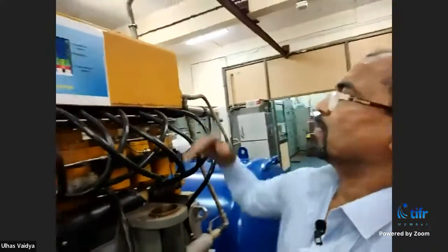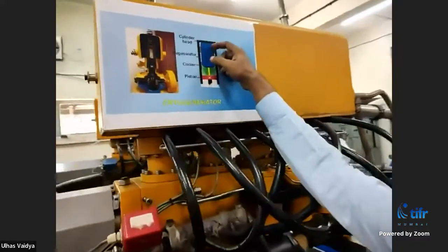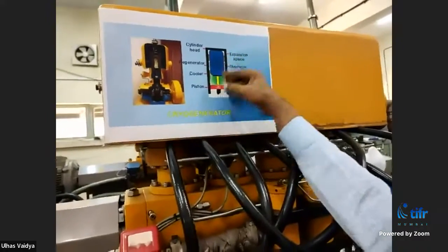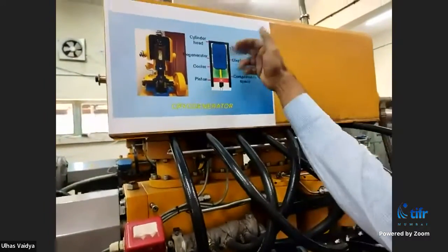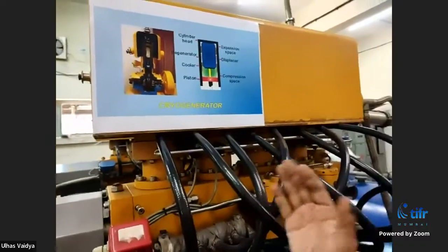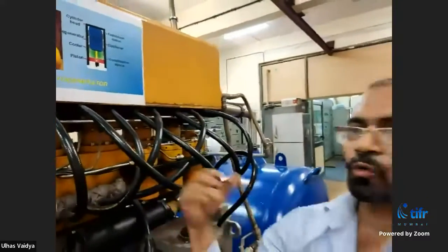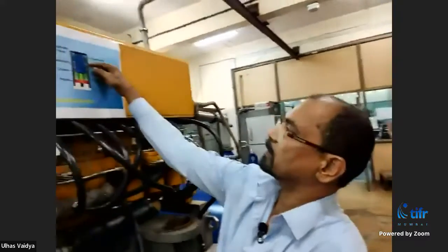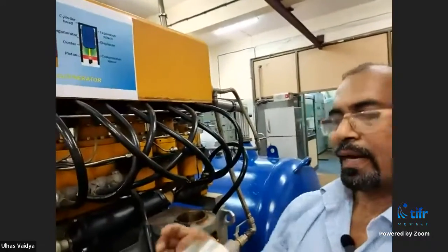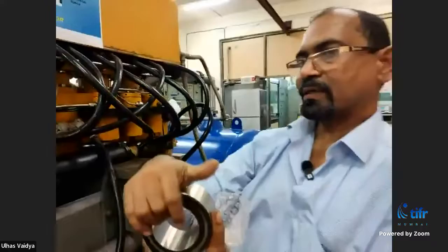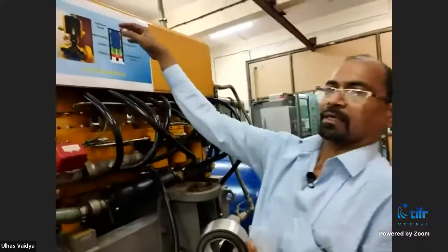After the regenerator, it goes to the expansion space where the displacer comes down and gas expands. When gas expands, its internal energy is rejected and temperature comes down to some 40-50 degrees, and that cold is absorbed in the regenerator and utilized by the next charge of gas. Every cycle, this temperature comes down more, and within half a minute, this temperature is down to minus 200 degrees Celsius.